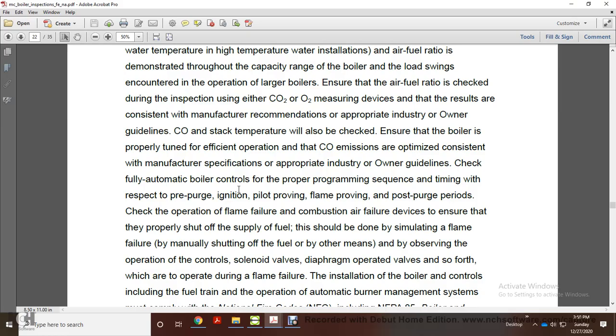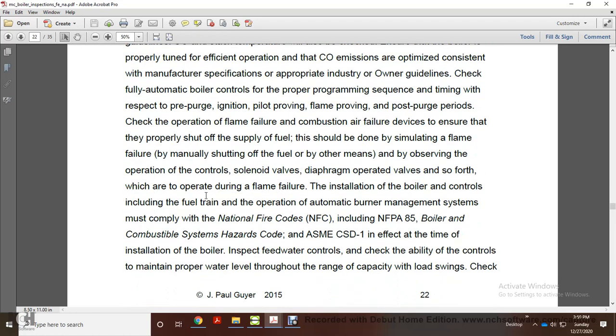Check, for fully automatic boilers, the control of the programming sequence and timing against the specification for the pre-purge, ignition, pilot valve proving, flame proving, and post-purge periods. Check operation of the flame failure and combustion air failure devices. This is to ensure proper shut-off of the fuel supply, and should be done by simulating the flame failure, mainly by shutting off the fuel, or by other means, by observing the operation of control solenoid valves, diaphragm operated valves, and so forth, which operate during flame failure.